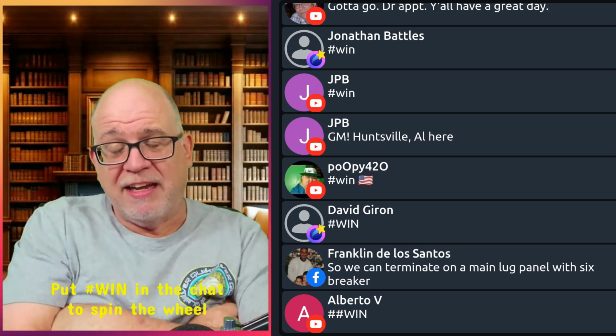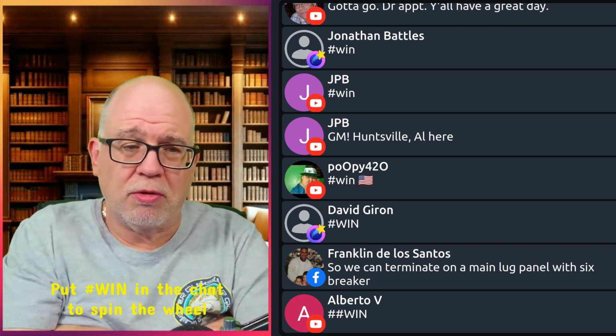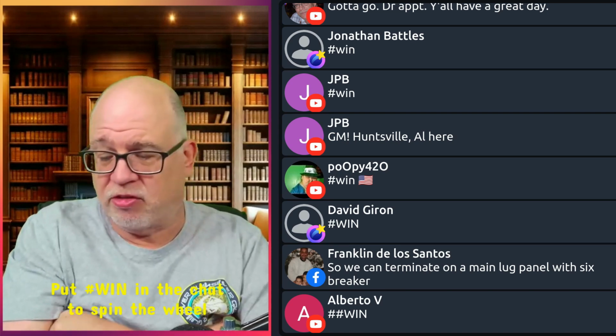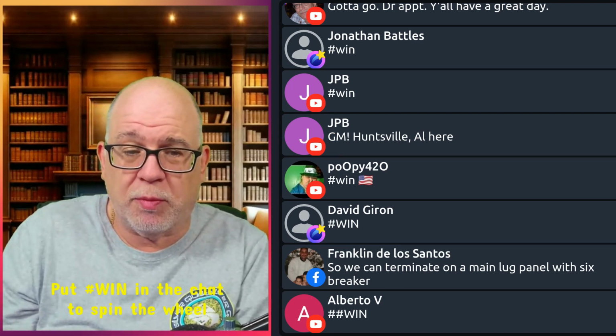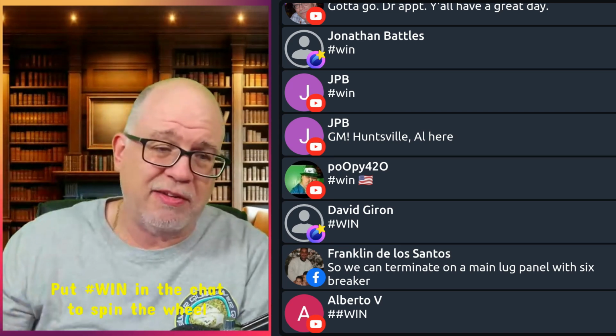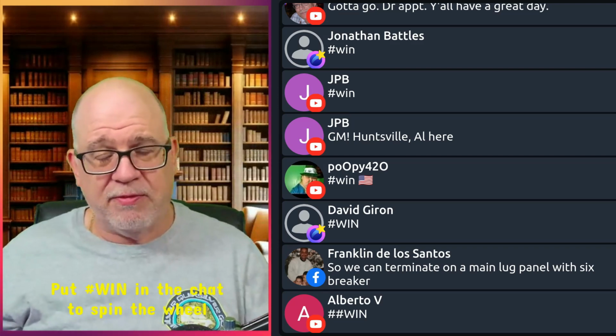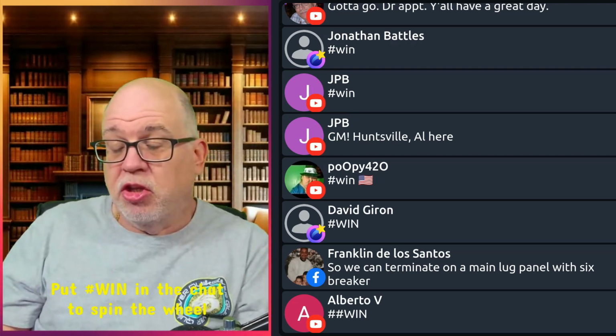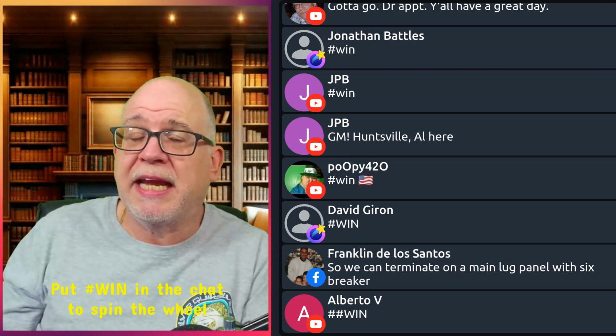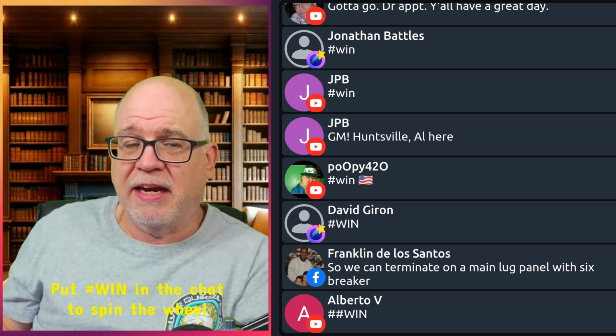Remember, when sizing transformers, we need to do a load calculation. We don't just willy-nilly this. You don't determine the kVA of a transformer by saying, I'll just make it a 75, I'll just make it a 50, I'll just make it a 25. You've got to know what loads are being handled by that secondary.